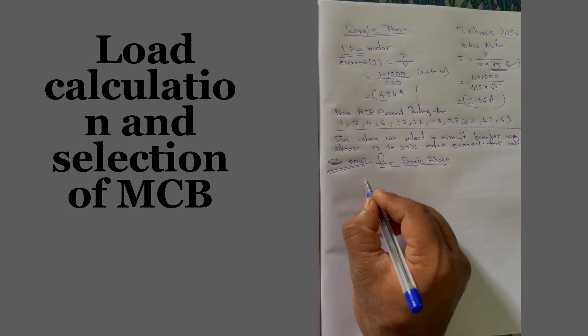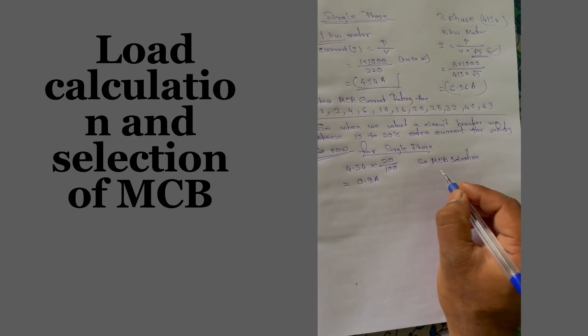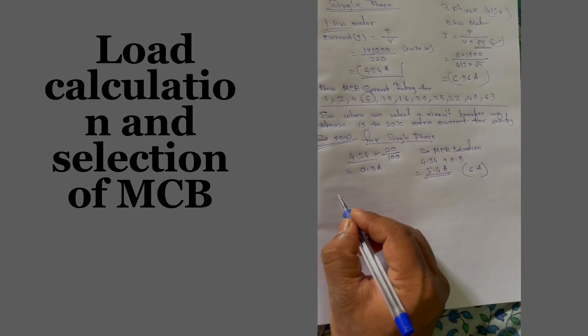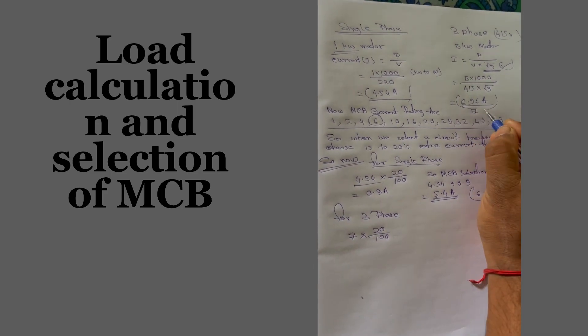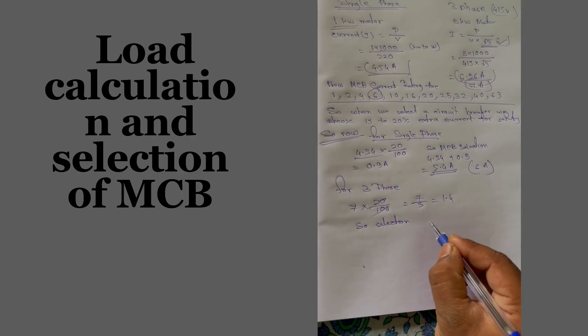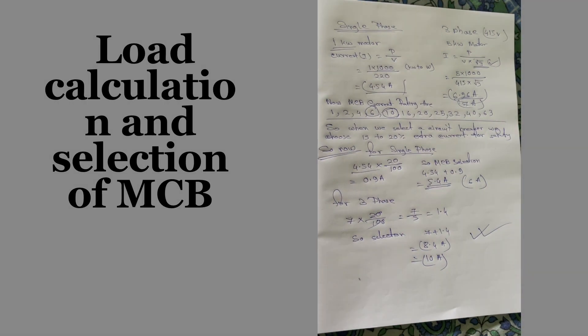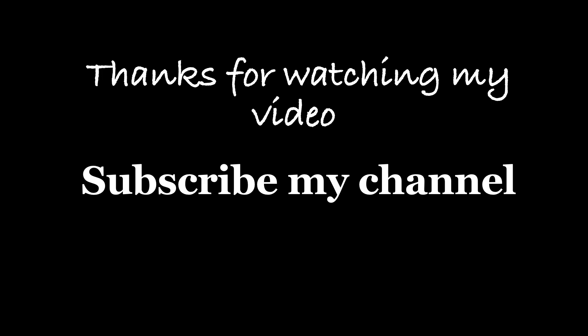For the single-phase one kilowatt motor, calculated current is 4.54 A. Adding 20% extra: 4.54 × 20 ÷ 100 = 0.91 A. Total = 4.54 + 0.91 = 5.45 A. Since 5.45 A is not a standard rating, we select 6 amperes. For the three-phase motor, calculated current is 6.96 A, approximately 7 A. Adding 20%: 7 × 20 ÷ 100 = 1.4. Total = 8.4 A. Since 8.4 A is not available, we select 10 amperes.